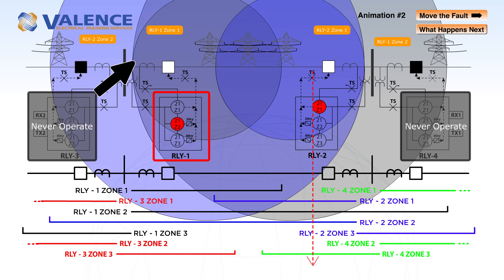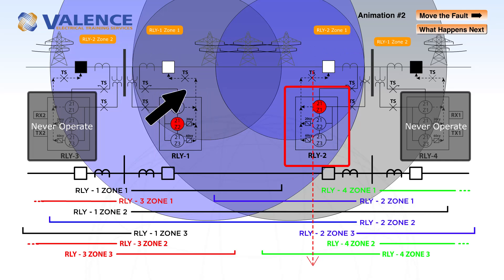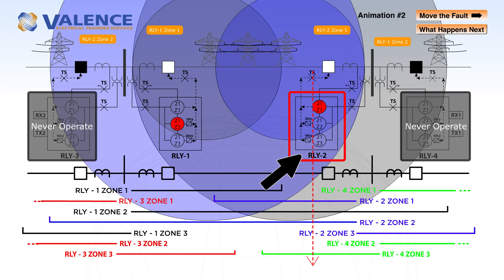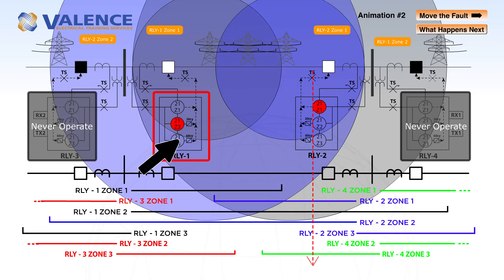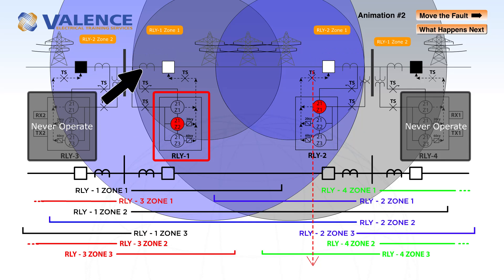Based on these tests, whenever there's a fault on the protection line, the worst case scenario is that one relay is going to operate instantaneously, and the other relay is going to operate about 20 cycles later.